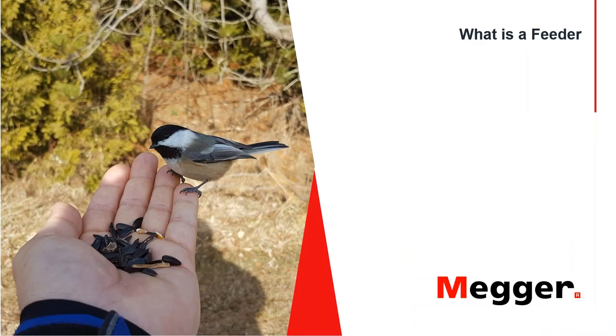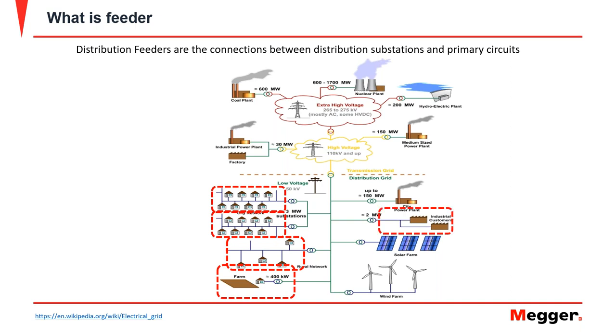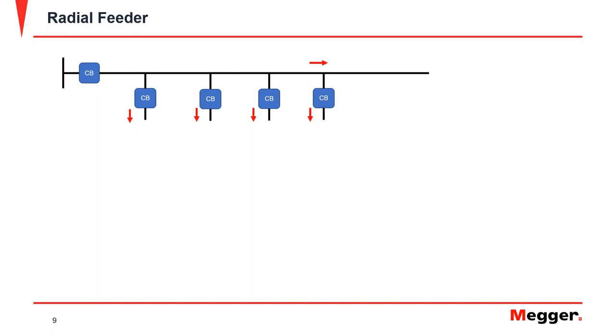In a distribution system, feeders are the connections between distribution substations and primary circuits, serving residential, industrial, or commercial customers. Radial feeders are the most common type, where every customer is connected downstream and there is no dual or multiple injection point into the feeder.